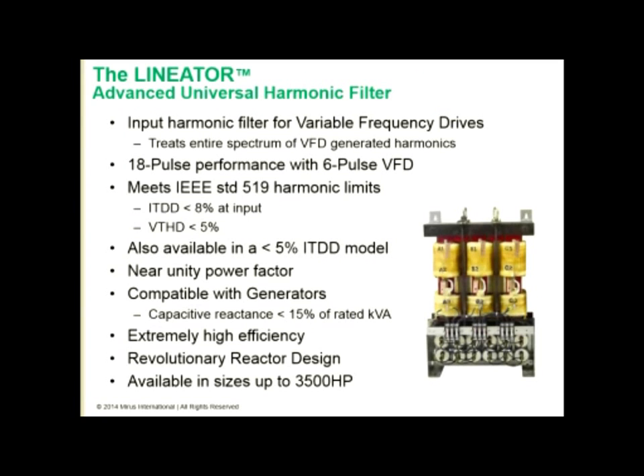Mirus offers Lineator, which is a passive harmonic filter. It is applied to the input of variable speed drives and treats the entire spectrum of harmonics generated by these drives. We can get better than 18 pulse performance when applied to a simple 6-pulse VFD. We'll meet the IEEE 519 harmonic limits of less than 8% total demand distortion at the input to the filters, and that will reduce the contribution of these VFDs to the overall distortion of the bus, ensuring less than 5% voltage distortion. We also have models now available with less than 5% TDD if this is a requirement for a particular application.